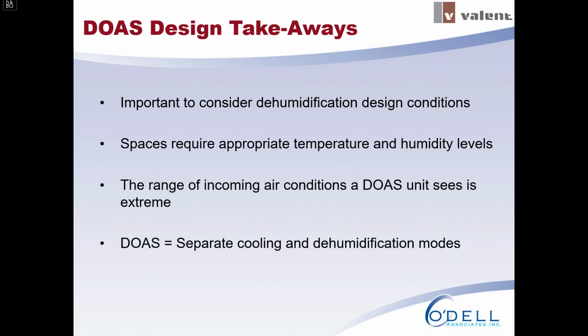So I'd just like to wrap up this DOAS section by highlighting some key takeaways of the things that we just talked about. So again, it's important to use that dehumidification design day condition for a DOAS unit especially. Spaces that require appropriate temperature and humidity levels, especially critical applications, you don't want to have spaces that are floating temperature and humidity wise, as that can lead to variations in the space. You want to be able to control dry bulb and humidity very tightly. If you start throwing in high ventilation rates, this can make it more challenging. And also the tolerance levels accepted by these spaces can vary greatly depending on the application.